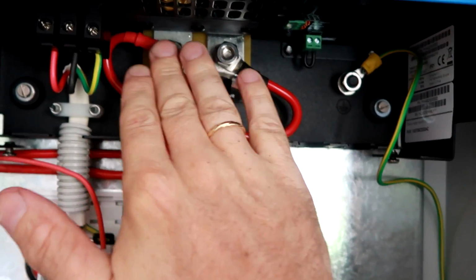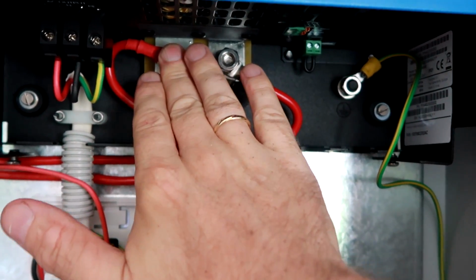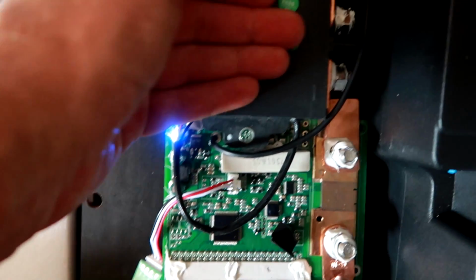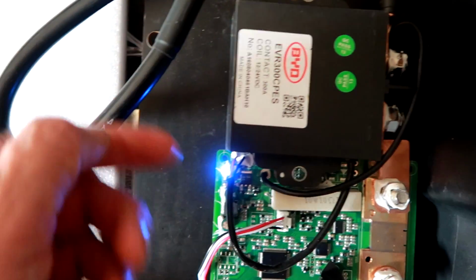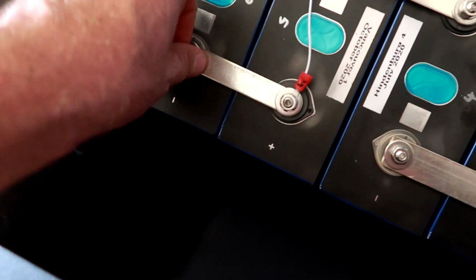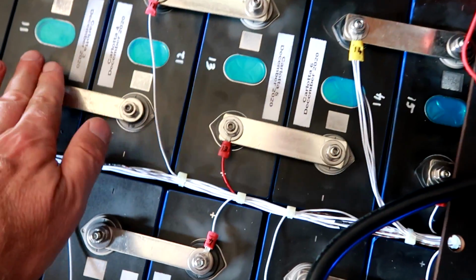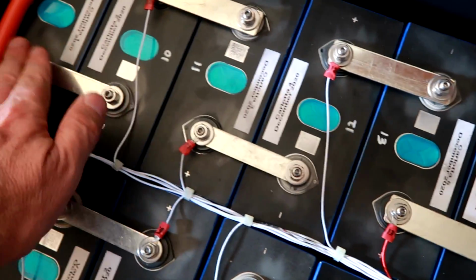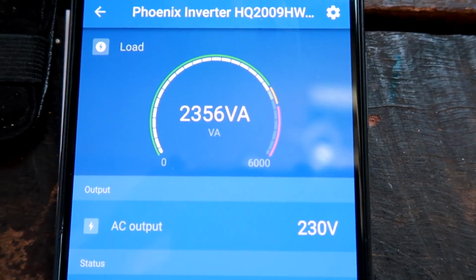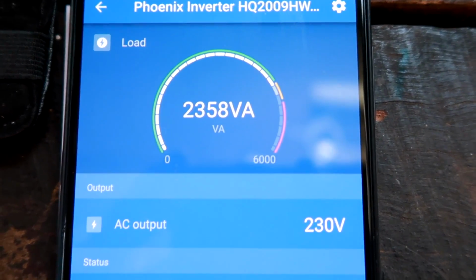Okay, because this is our first big load test now, I just want to make sure there is no heat. That is all good. Our relay is on. Well, I guess it doesn't make a difference if it's on or off. And I quickly do a hand check here of temperatures of the terminals. But at the moment there's only 800 watts coming from the battery now. So the rest is coming directly from our solar. Okay, I now cranked up the charging speed to 10 amps inside the car.